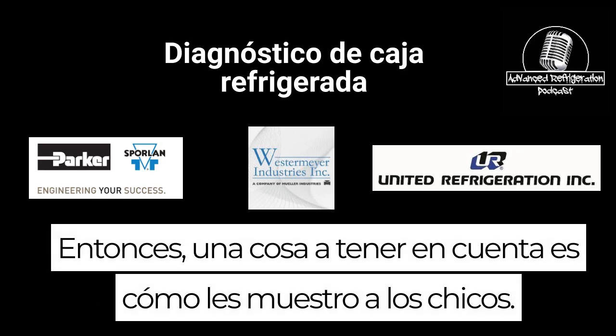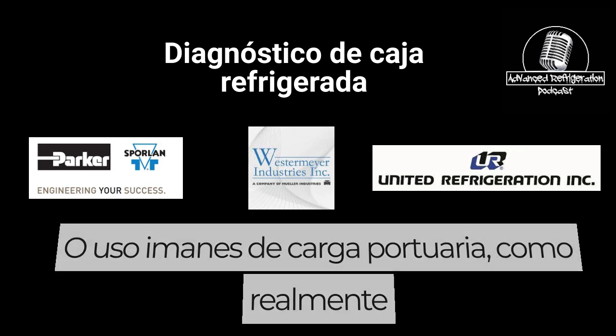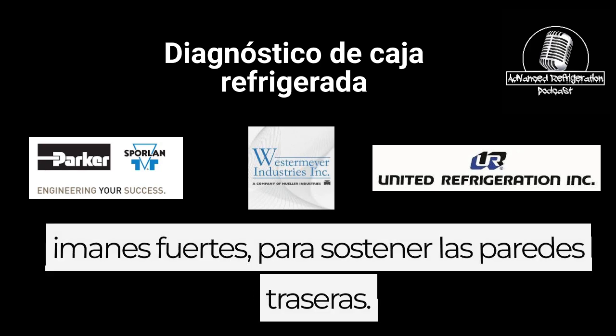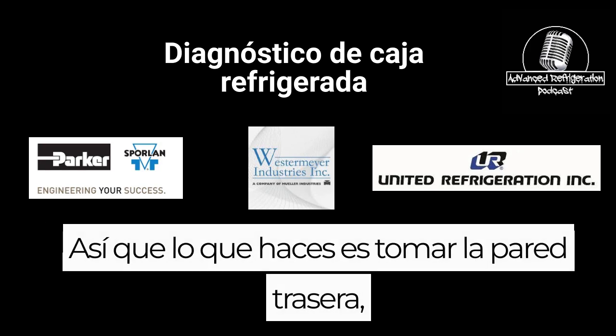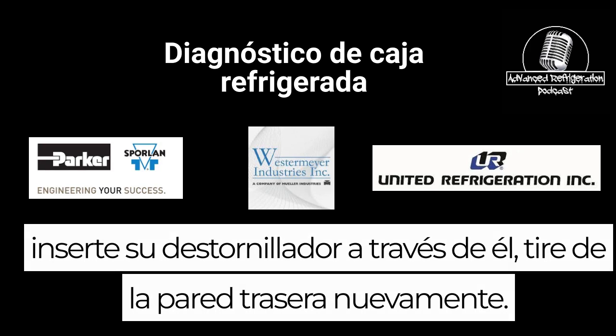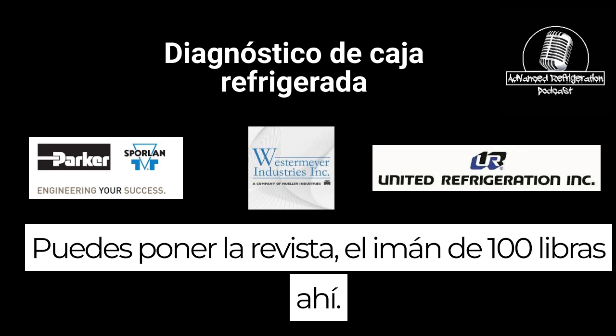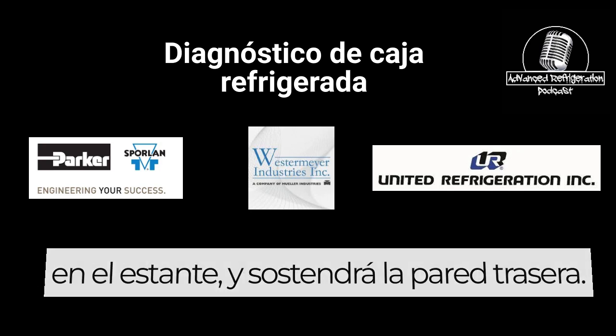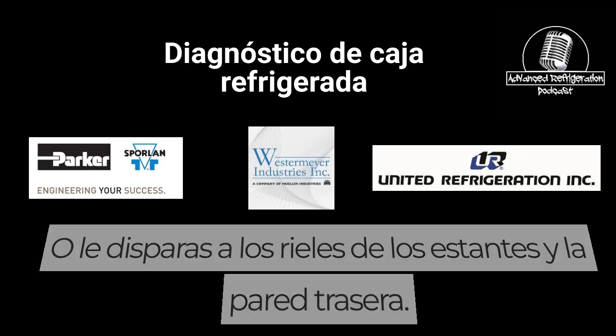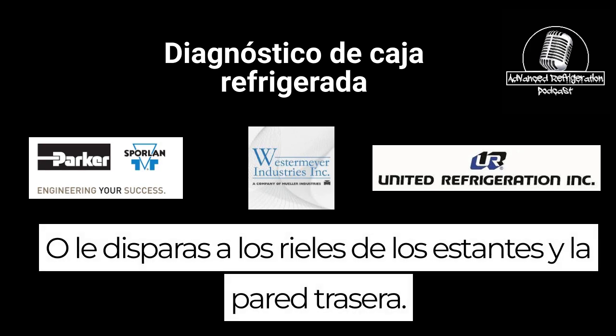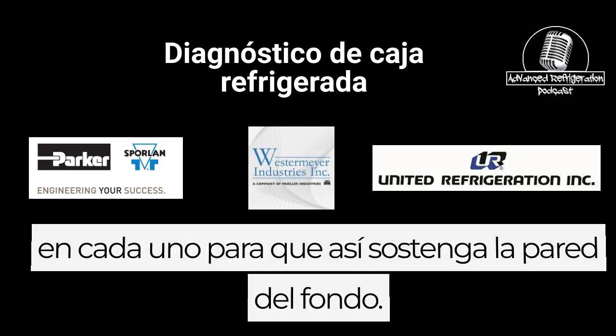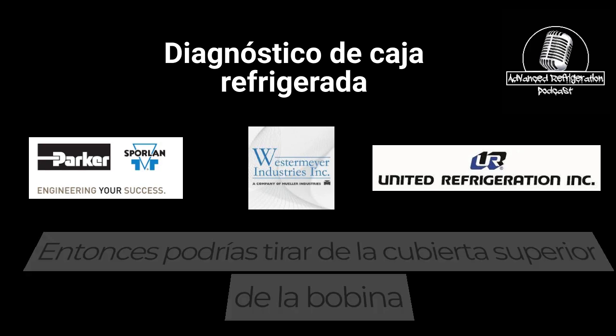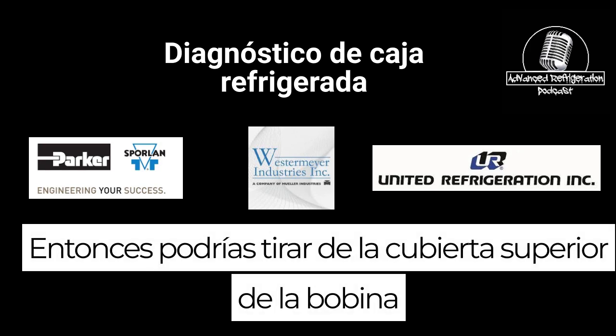So one thing to be mindful of is how I show guys to do it. I do it two ways. I either use Harbor Freight magnets, really strong magnets, to hold up the back walls. What you do is you take the back wall, stick a screwdriver through it, pull the back wall again, and you put the 100-pound magnet on there, right on the shelf, and it'll hold the back wall up. Or you shoot self tappers in the shelf rails and the back wall on each one, so that it holds up the back wall, so you could actually pull the top coil cover off.